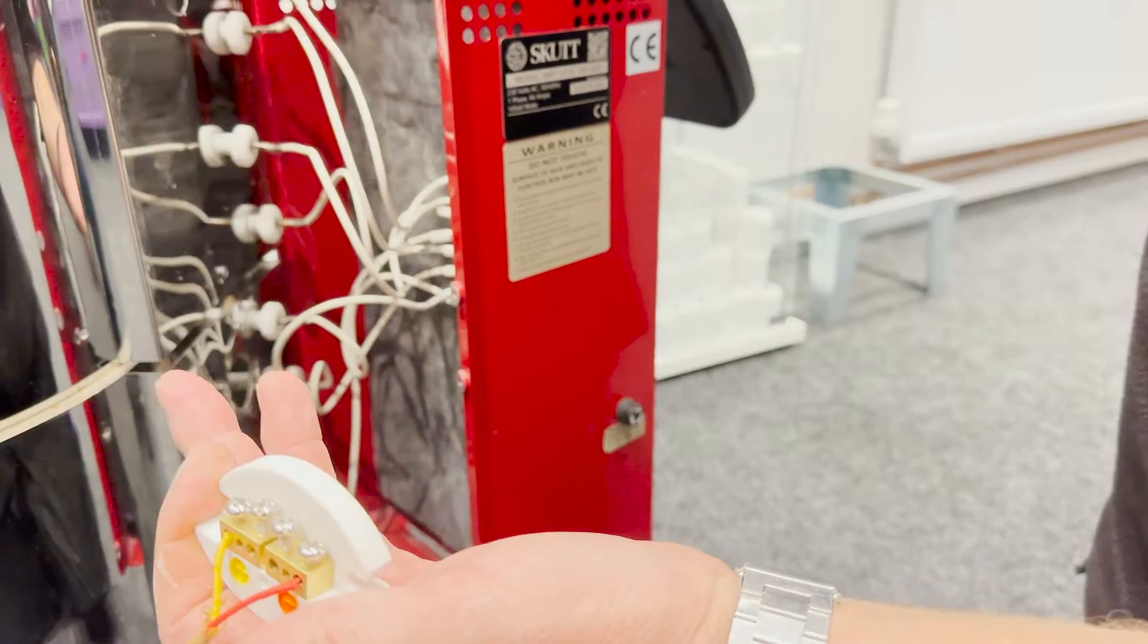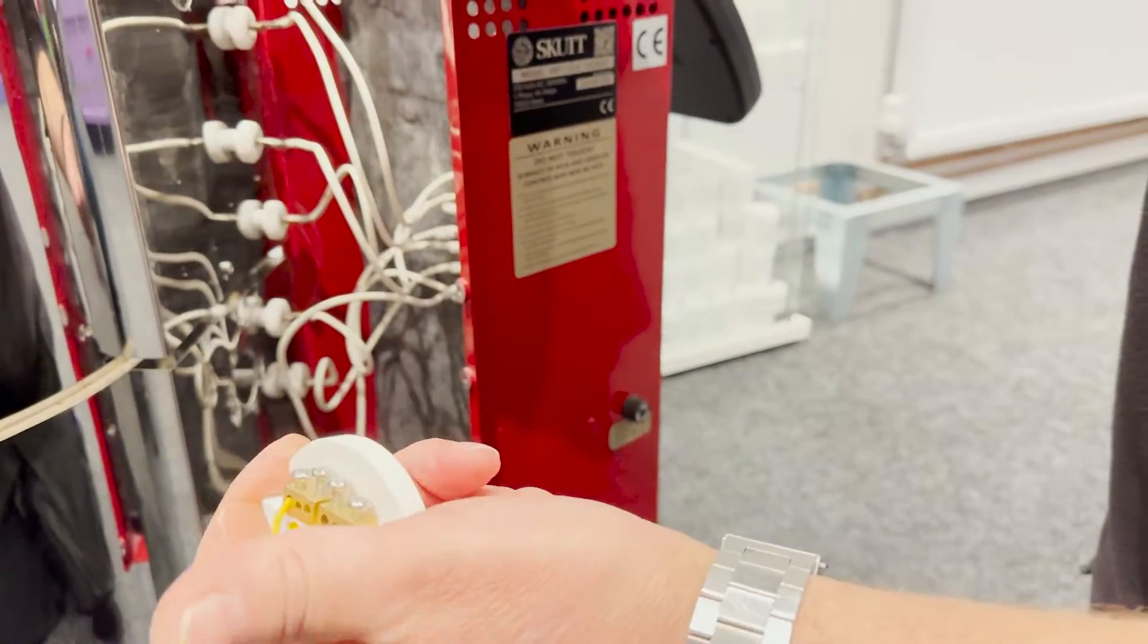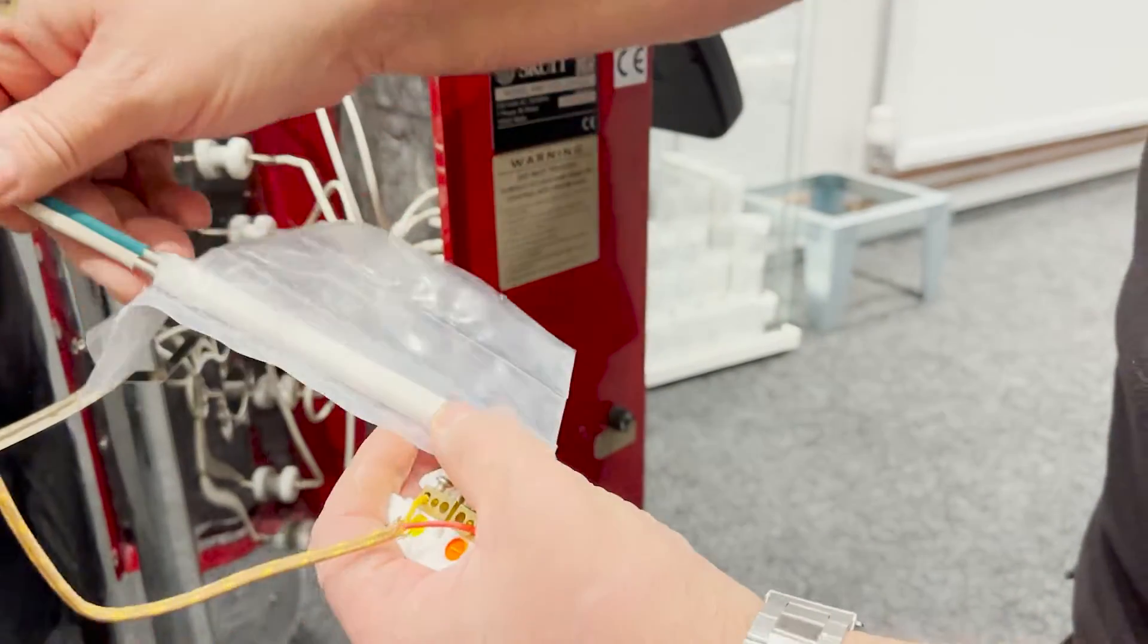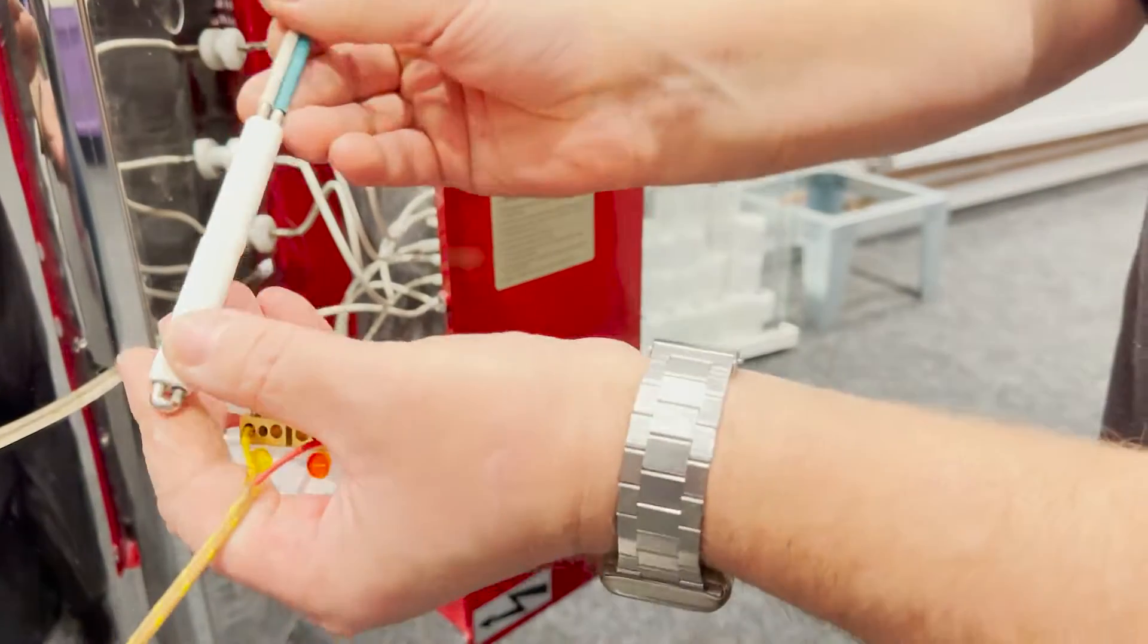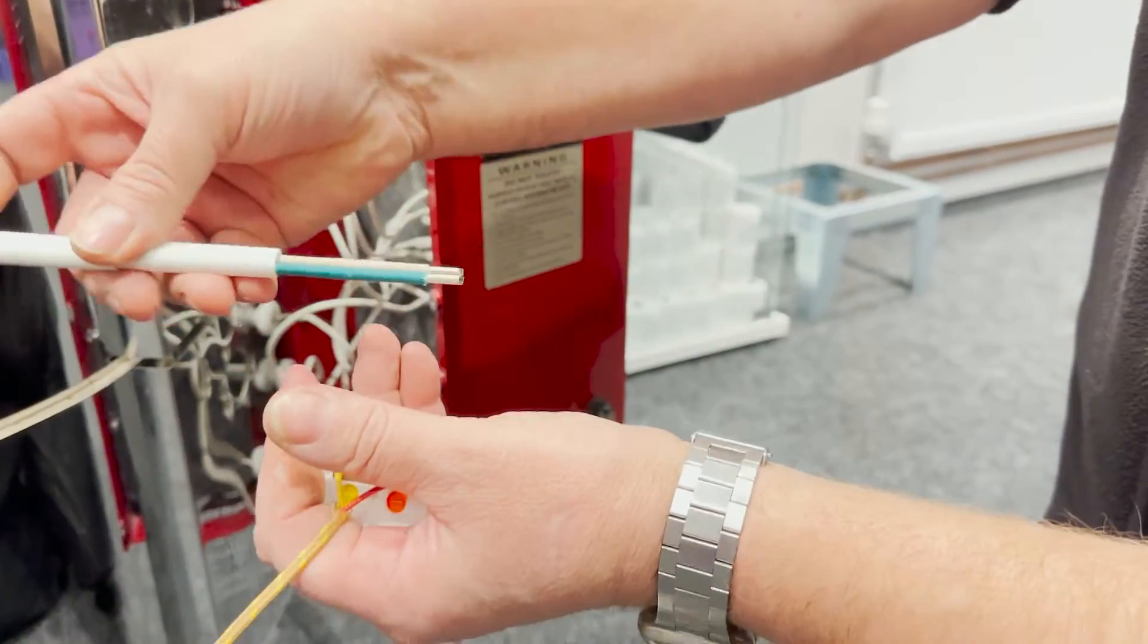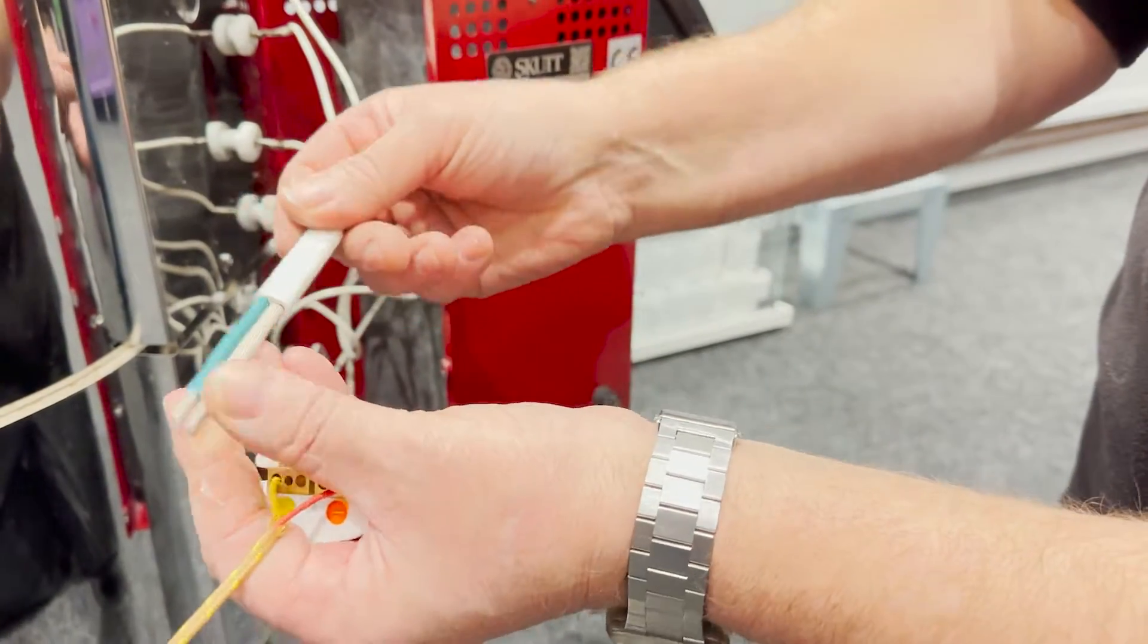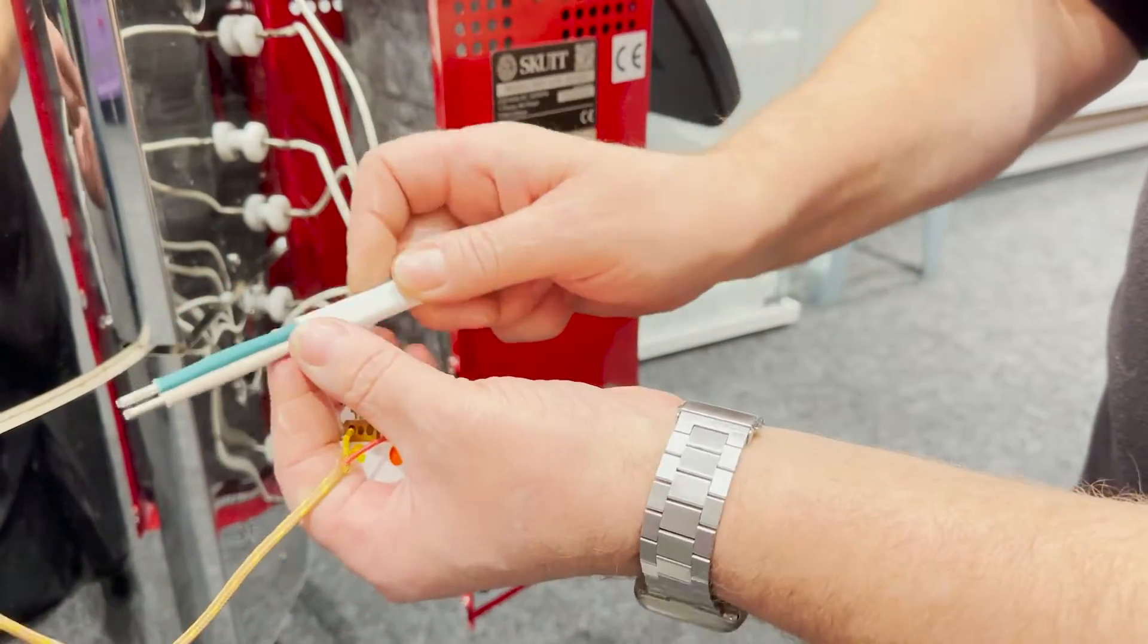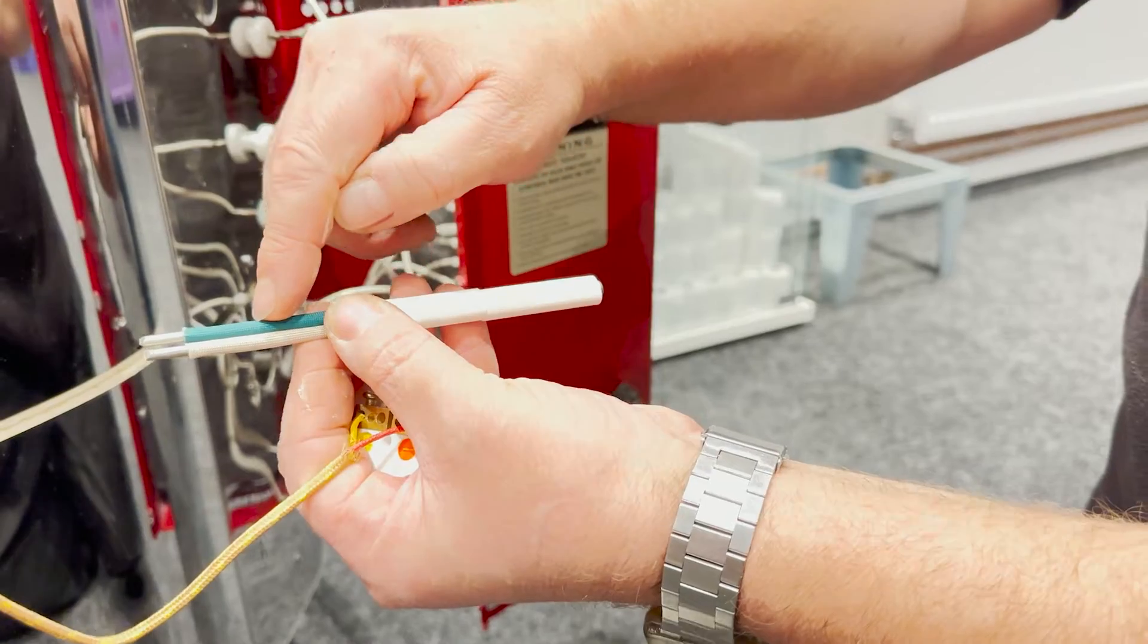Get your new thermocouple. When it's supplied, because this is the UK model, the green is positive and the white is negative.